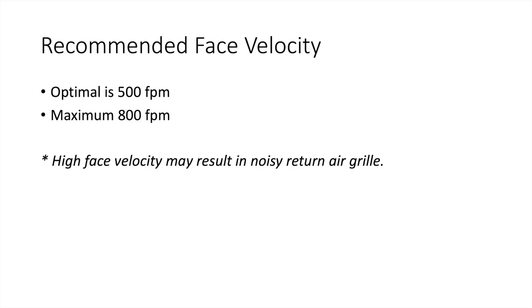So, if you are replacing your typical boring old grill with a more stylish one, the more stylish ones usually have less free area. You need to increase the grill size of your new grill in order to keep the noise level low. If you really have no choice, a face velocity of 800 feet per minute may still be acceptable, depending on the location of the grill. If you exceed that, the noise is usually too much.